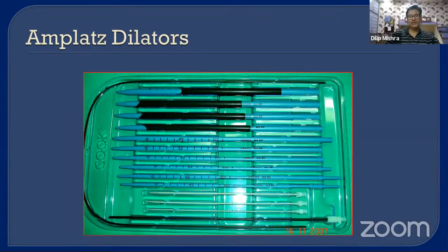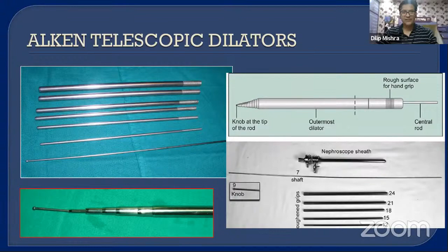Then comes the Alken's telescopic metal dilators. This was initially popularized by Dr. Peter Alken, and here you can see there is a long central rod with the oval tip, and there is a set of 8 dilators which are moving in a step of 3. So 8 French central rod is there, followed by 9, 12, like that. It will go on to 30 French, and you can dilate it up to the level which you want the dilatation to be. And then after the last dilator, you can pass on the Amplatz sheath, and the whole system comes out smoothly through the Amplatz sheath. So this is the Alken's telescopic metal dilators. These are some finer points of these telescopic dilators.